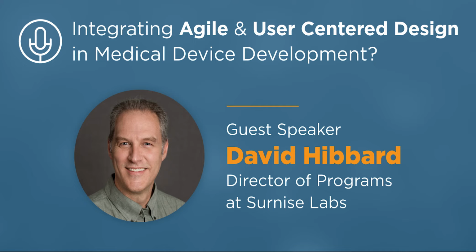If there's some input I can offer, or if we're defining acceptance criteria and maybe there's a use error that I know is related to this design, or a certain feature mitigating a potential use error, we can add some language to the acceptance criteria to say, let's make sure that this use error is mitigated. Ultimately, from a human factors perspective, it comes down to mitigating use-related risk. I'd say that's one key component of how that aligns with my contributions.